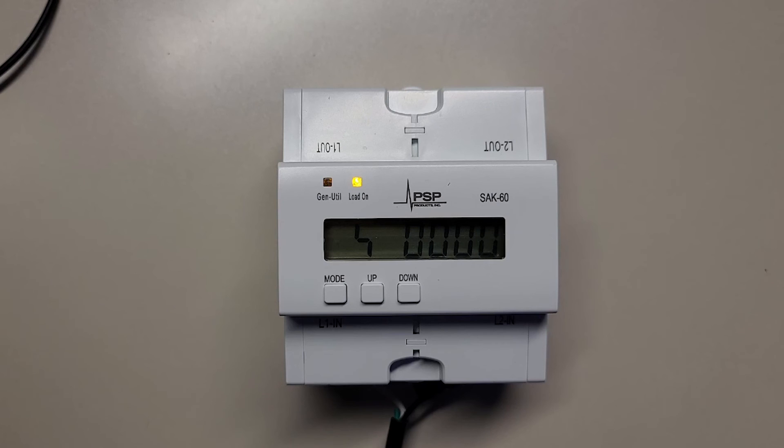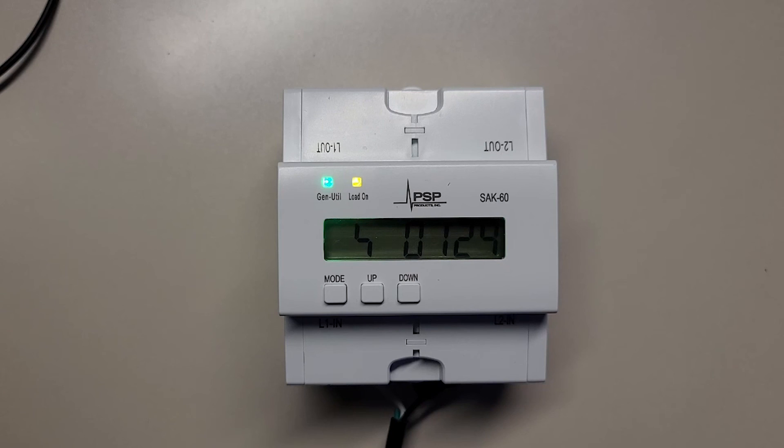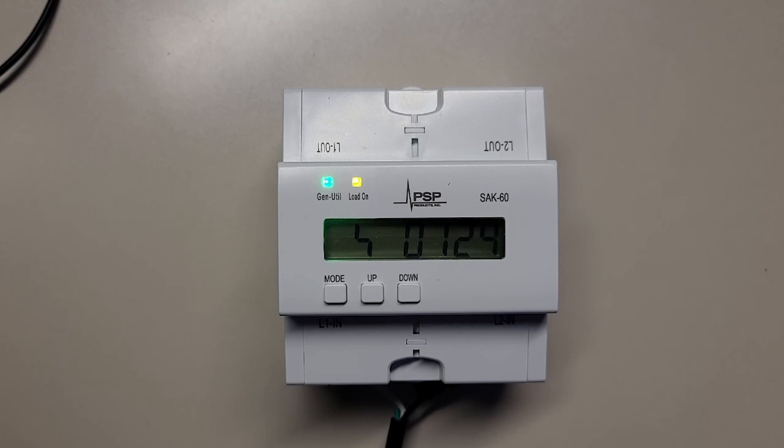Now, when the power goes out, the generator starts and transfers. When generator power hits the line side of the SAK-60, it will analyze the AC waveform. When it recognizes a generator waveform, the gen utility light will turn green. The load light will remain off because the relay will remain open.